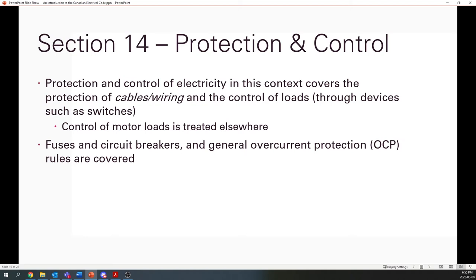The circuit breakers and the fuses that we have are really to protect the wiring, and that is for fire prevention. As I was saying before, if you run too much current through the wire, it gets too hot, and you can have a fire. That is really the purpose of overcurrent protection and circuit breakers. It's not to protect the load, it's not to protect you. If you get shocked by a wire, even with a normal 15 amp circuit breaker, you're going to be dead a long time before that circuit breaker trips. The circuit breaker might never trip.